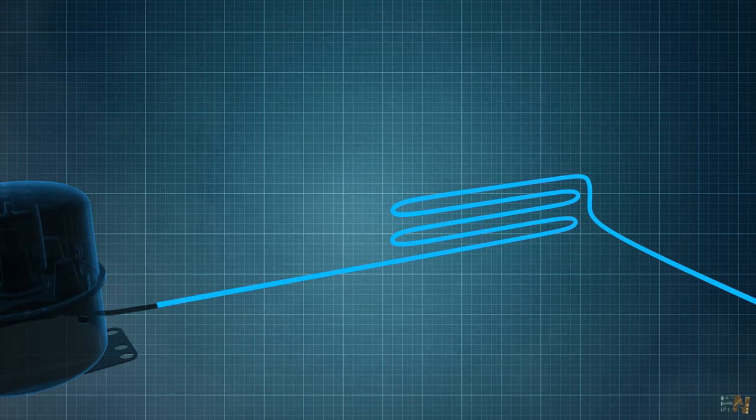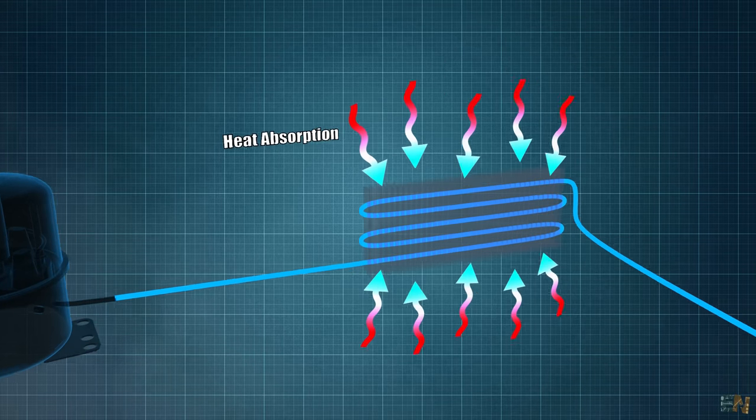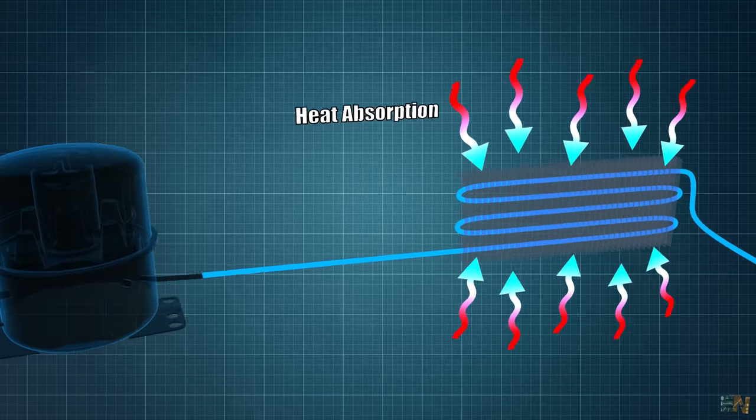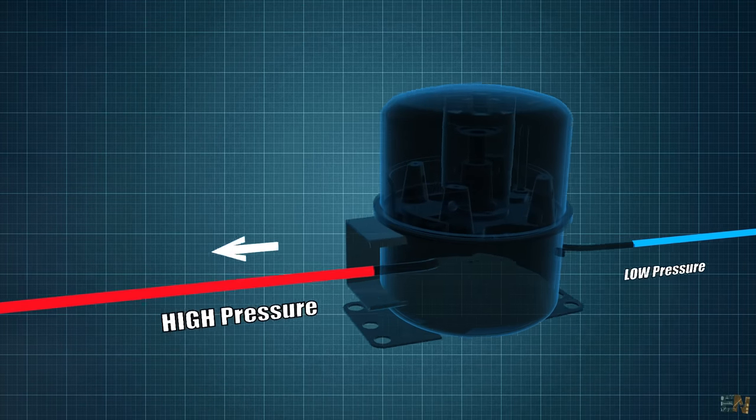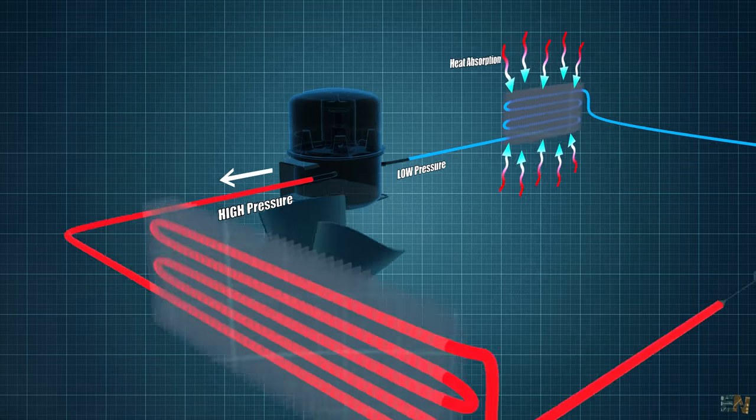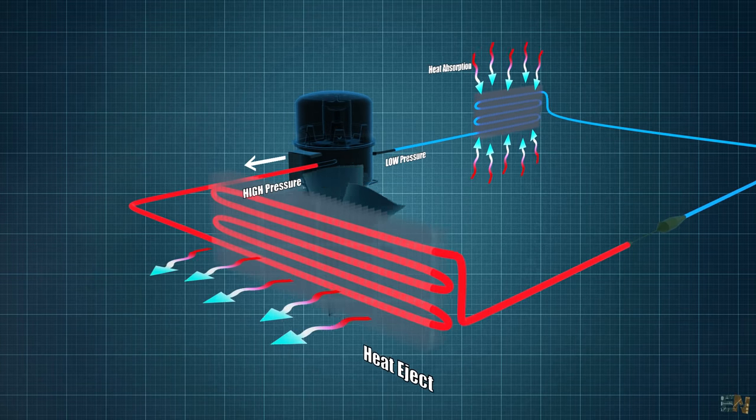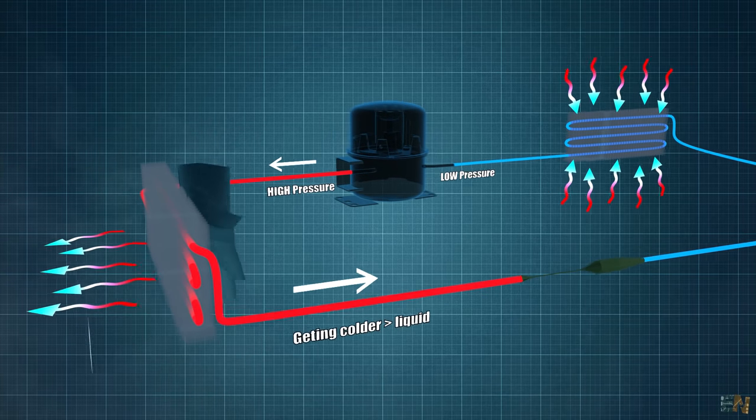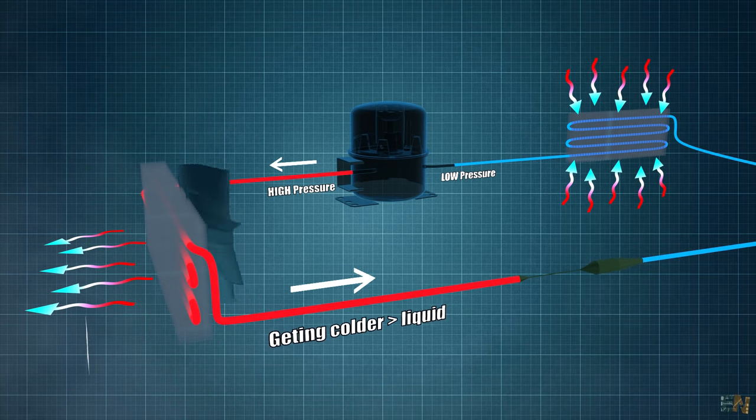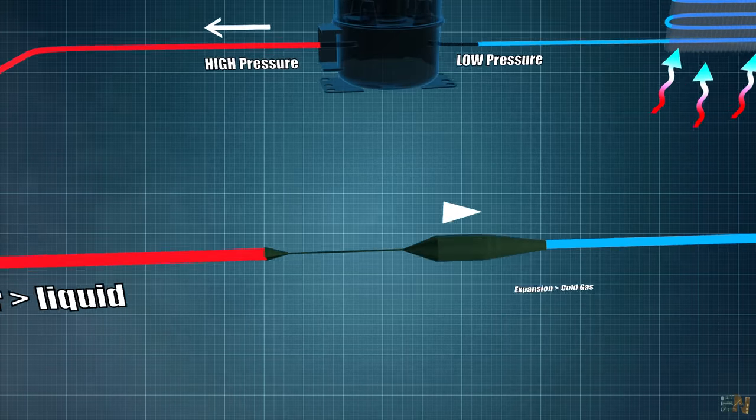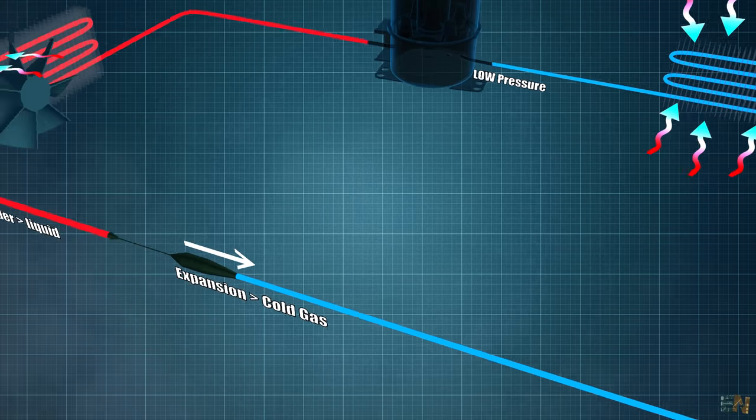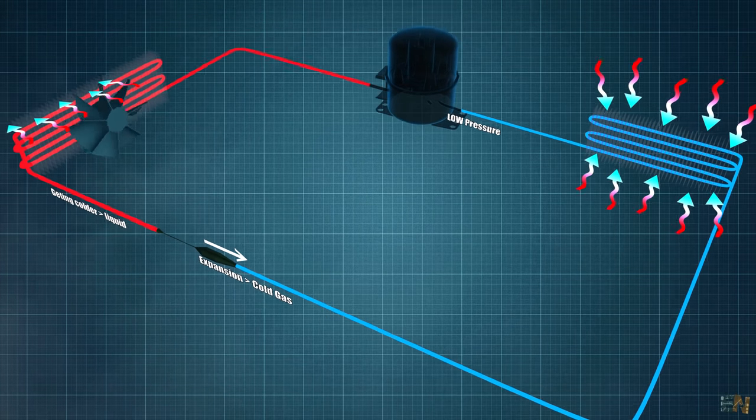Let's see this process once again but faster. This cold refrigerant will absorb the heat from the room and by that will get a bit hotter. The compressor increases the pressure once again and this will get even hotter. On the condenser, the heat is ejected on the outside and in this process the refrigerant is lowering the temperature and changing back into a liquid. Finally, when this liquid passes rapidly from high pressure to low pressure, it turns back into a gas and at very low temperatures. From here, the process repeats on and on.